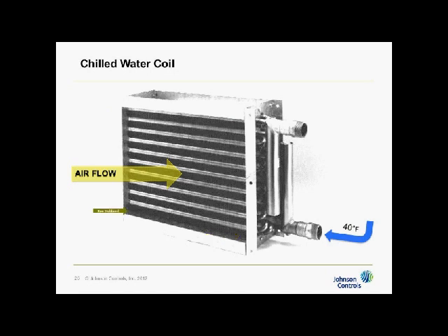These very corners of the coil that you see here are the places where the coil starts to get dirty. And as it gets dirtier and dirtier, it'll form sort of a donut shaped, where the very center of the coil is clean and the very edges of the coil are dirty. So if you had a light on the other side of the coil and you shone it through and you look through it, you'd see very light in the middle and kind of a donut getting darker and darker.